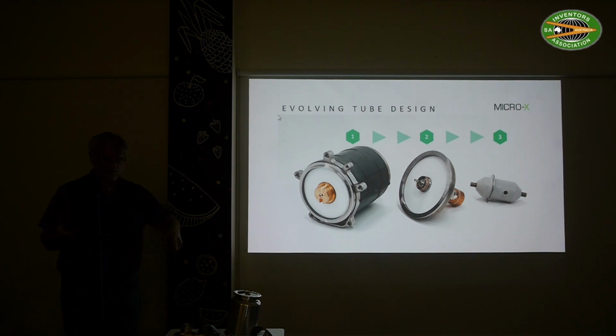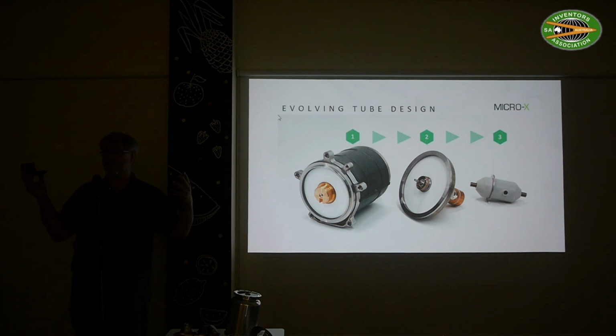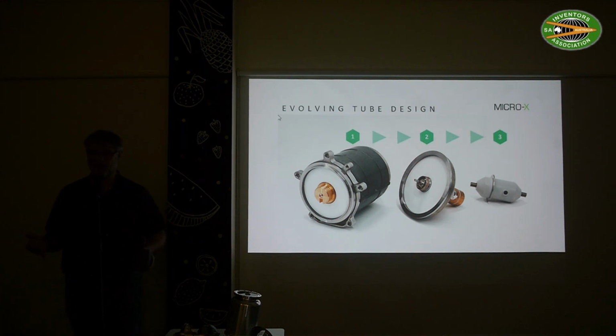This one operates at 120 kilovolts; if you go to 160 kilovolts, which penetrates better, this shielding wouldn't be enough. Jumping forward a bit, in that baggage scanner, a significant portion of the unit's weight is actually lead - shielding in the doors, shielding in the panels. We open the door to access it, but when it closes it becomes one enclosed lead box. That's why the machine is about 700 kilos, so heavy you really need a forklift to move it.